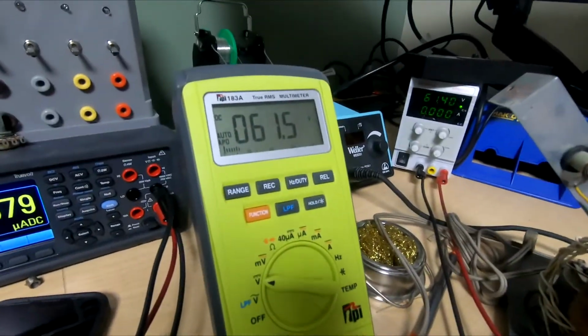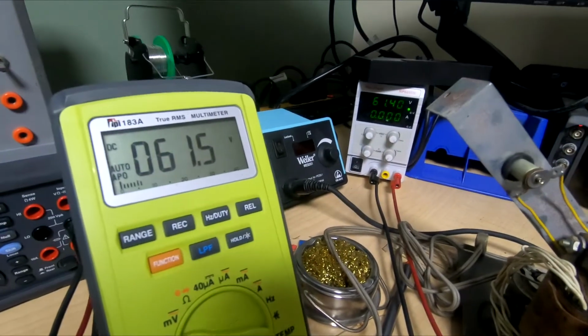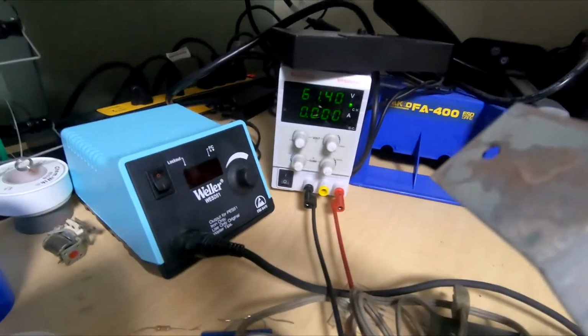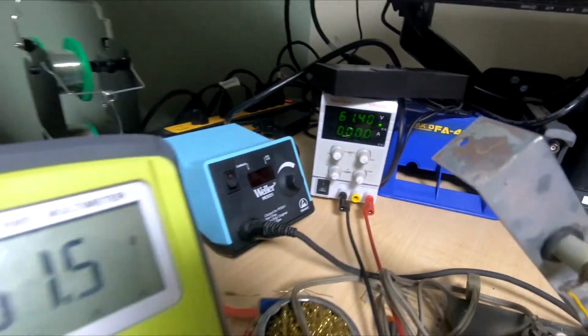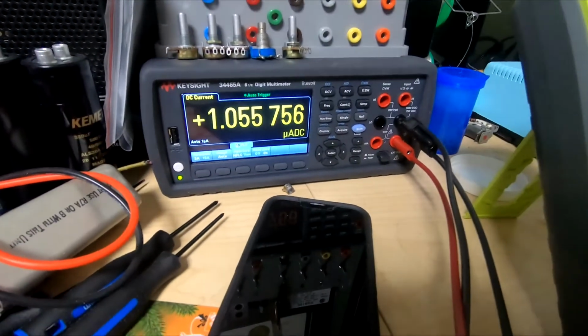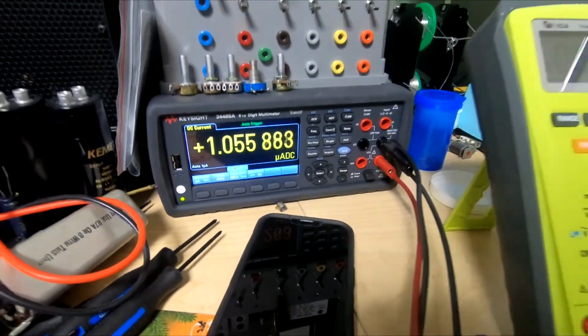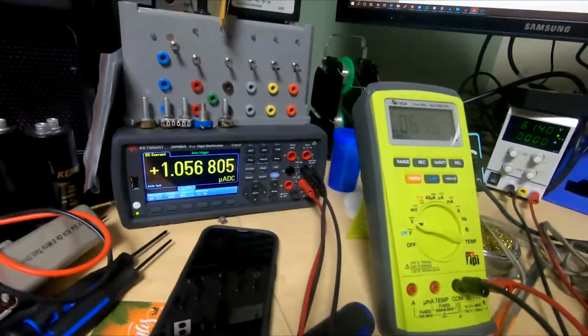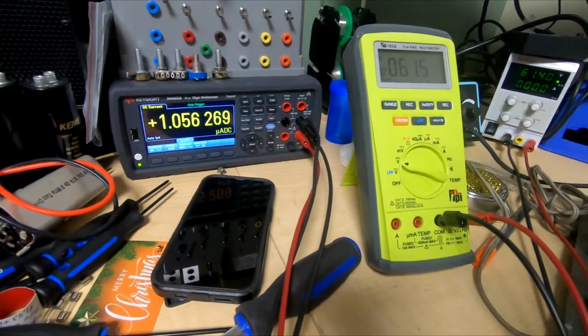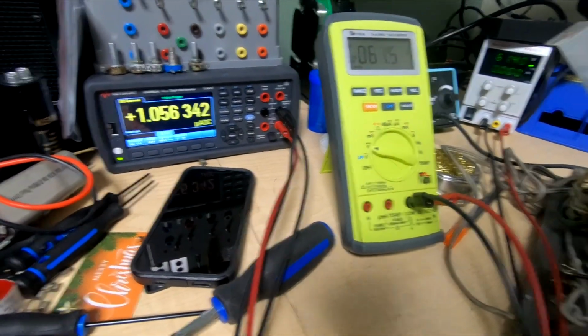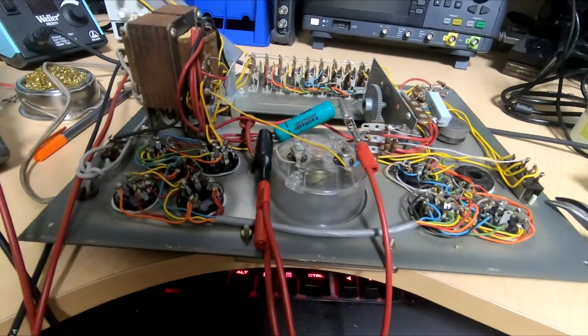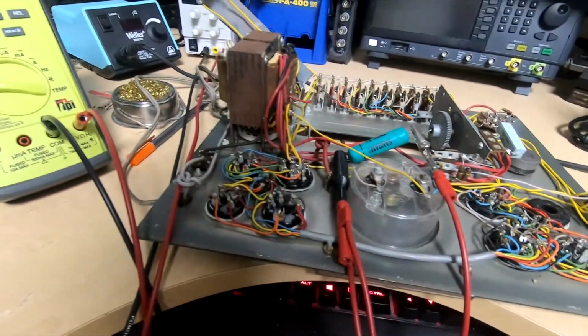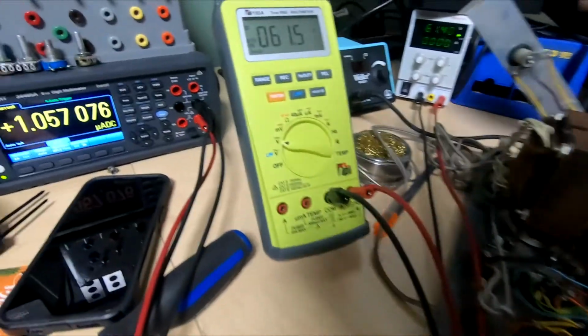You can see I have it charged up to 61 volts there. The DC supply shows the same thing, and I'm seeing about 1 microamp of leakage through that capacitor, so it's actually not that bad. Obviously it's nowhere near the 600 volts it's rated for right now, but 60 volts is as much as I can go.